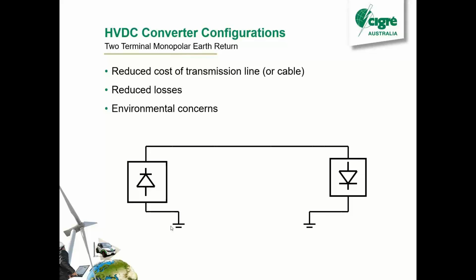So yeah, the losses are pretty good, much improved in monopole with earth return. The only issue is you can have some environmental concerns when you do earth return. You can end up with current going places where you don't want it to, like it can go into nearby buried structures and cause corrosion in fencing or pipelines. And it can also go up into your AC network through grounded neutrals and cause saturation of the transformers. So a lot of jurisdictions don't allow it.